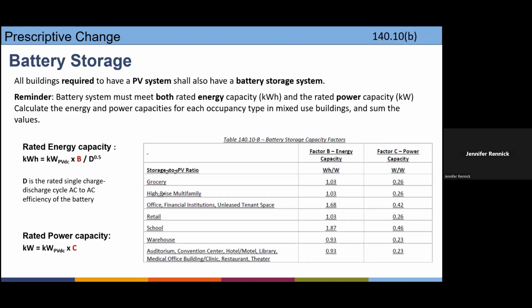And then for battery storage, there is a similar situation, where you use some math to figure out how much battery storage you need based on those same occupancy types. But it's not based on climate zone, just straight up occupancy types. And you can do it if you're the architects or mechanical engineers, or you might have your electrical engineer look at this with you or for you, but it begins to tell you what size PV battery system you need based on the rated capacity of your PV system that we just calculated in the previous calculation.